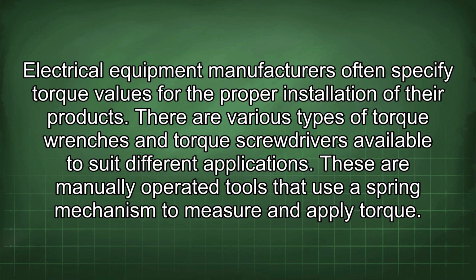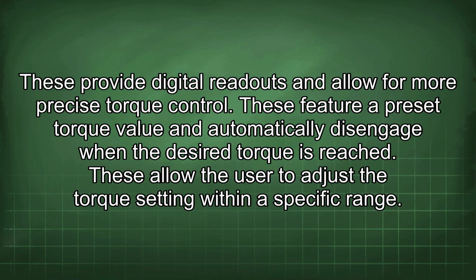There are various types of torque wrenches and torque screwdrivers available to suit different applications. These are manually operated tools that use a spring mechanism to measure and apply torque. These provide digital readouts and allow for more precise torque control. These feature a preset torque value and automatically disengage when the desired torque is reached. These allow the user to adjust the torque setting within a specific range.